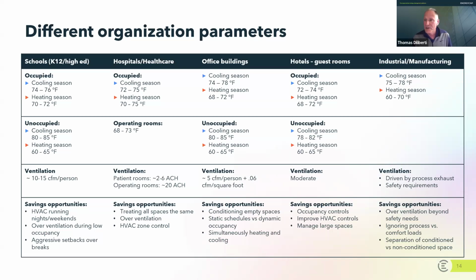So the ventilation standard was initially very high. We had the energy crisis occurring in the 70s and 80s, and they squeezed the ventilation standard down from 15 down to 5. What happened at that point is we had sick building syndrome come in. So buildings began to show more problems because the ventilation wasn't high enough. And so what happened was the pendulum swung from 5 CFM up to 15.